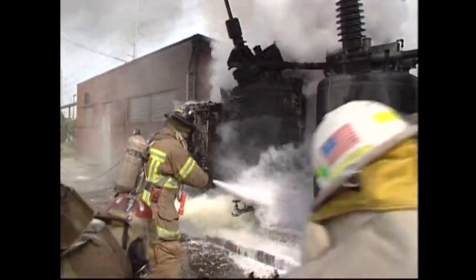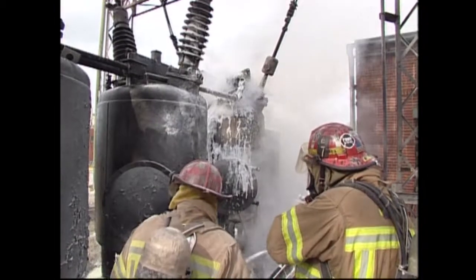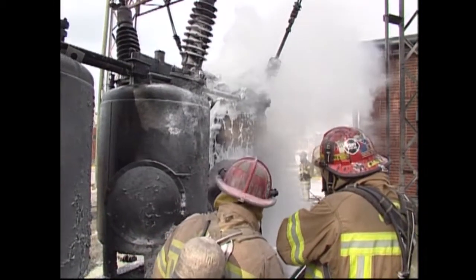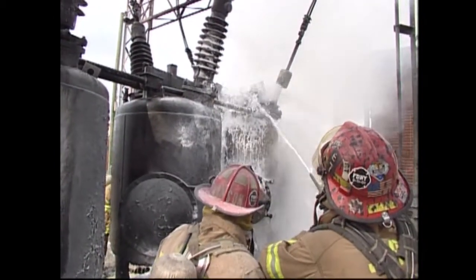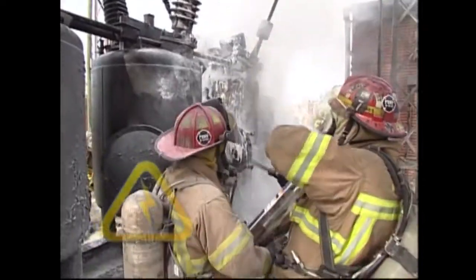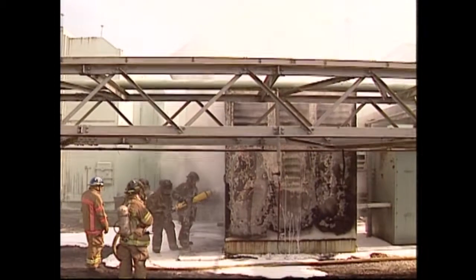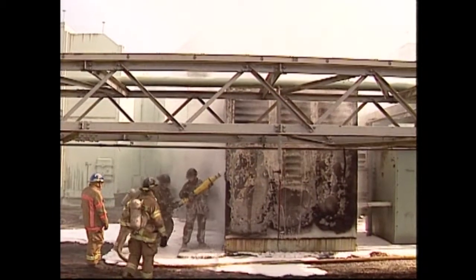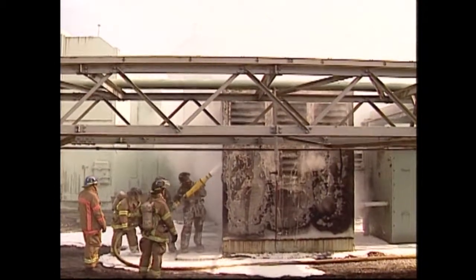However, the fire may continue burning inside the equipment. Reignition is not uncommon, and the oil may burn for an extended period of time. Burning could start and stop for days. Be aware that the oil vapors are also capable of exploding. So full PPE and safe distances from equipment need to be maintained.